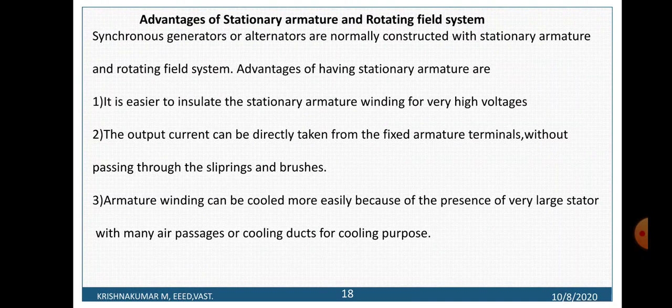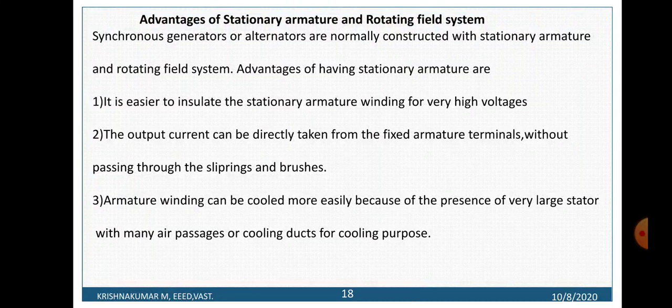Advantages of keeping the armature winding stationary and the field in the rotor: Synchronous generators or alternators are normally constructed with a stationary armature and rotating field system. First, it is easy to insulate the stationary armature compared to a rotating armature. Second, the output current can be directly taken from the fixed armature terminals without passing through slip rings and brushes. Third, armature winding can be cooled more easily because of the presence of a very large stator with many air passages or cooling ducts.